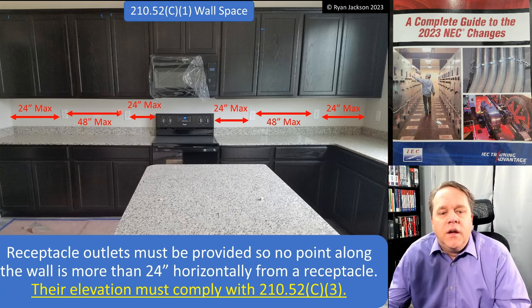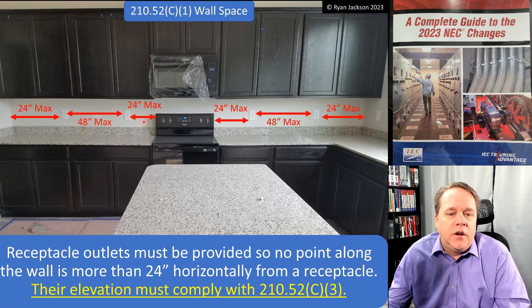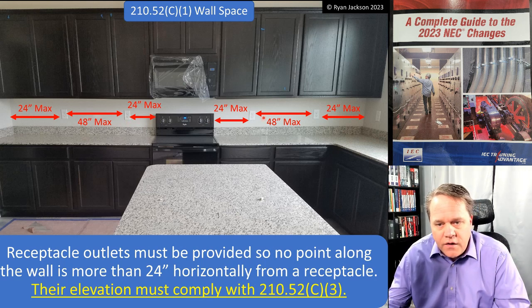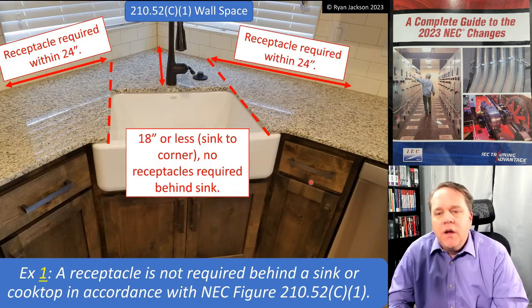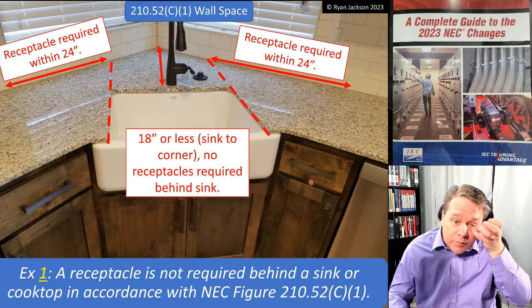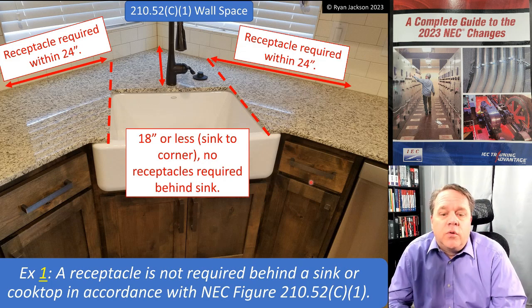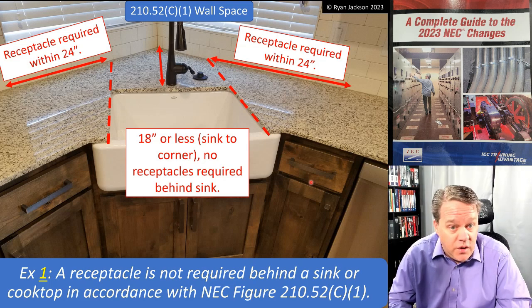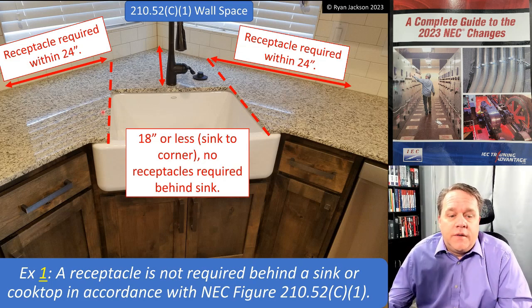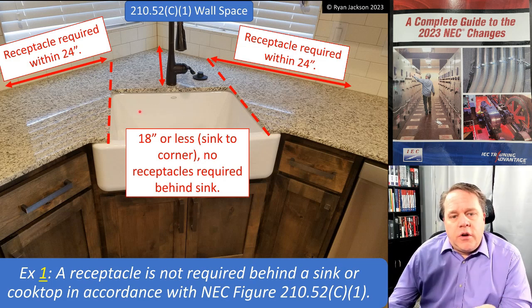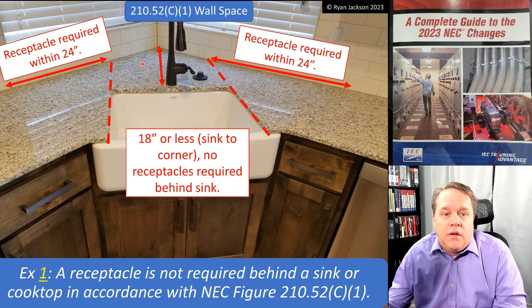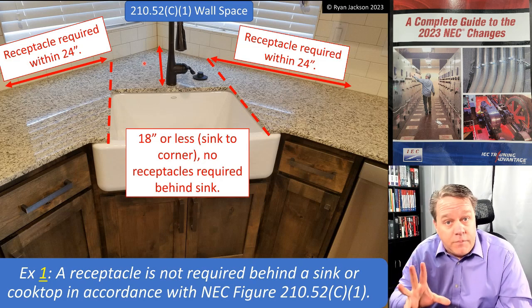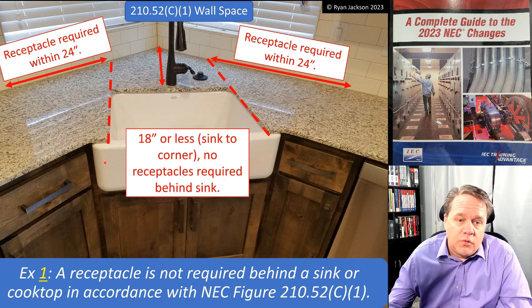Butt the tape into the left, pull it to the right — you need a receptacle within two feet, then four feet, then butt it into the range and pull left, needing a receptacle within two feet. That measurement rule hasn't changed. There's still an exception: a receptacle is not required behind a sink or cooktop. Per Figure 210.52C1, if the corner-to-back-of-sink distance is less than 18 inches, no receptacle is required behind the sink.